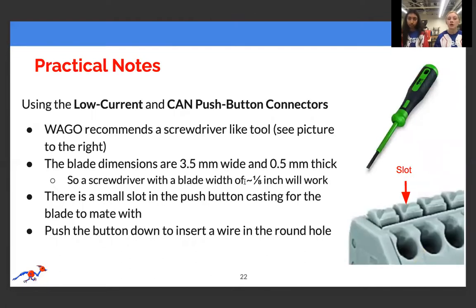For the low current and CAN push button connectors, we recommend using a Wago tool, a screwdriver-like tool. The blade dimensions are 3.5 millimeters wide by 0.5 millimeters thick, so a screwdriver with a blade about 1/8 inch would work as well. There's a small slot to push on the button casing for the blade to mate with. Push the button down to insert the wire, and it will lift the gate.